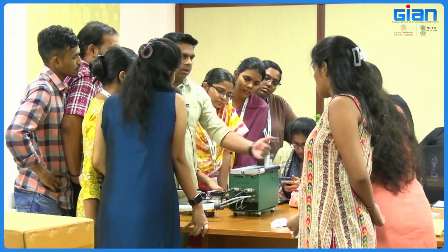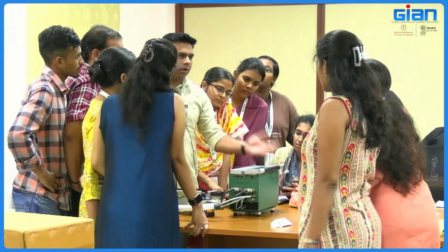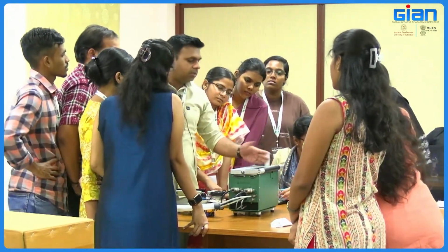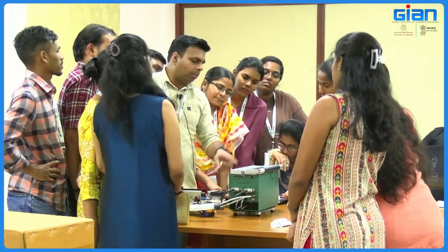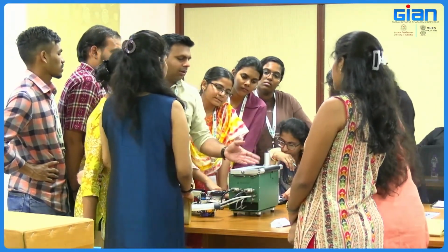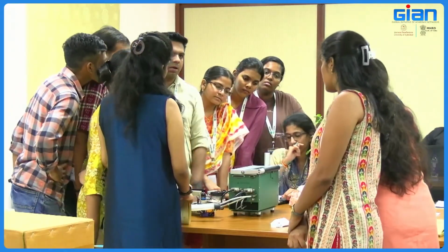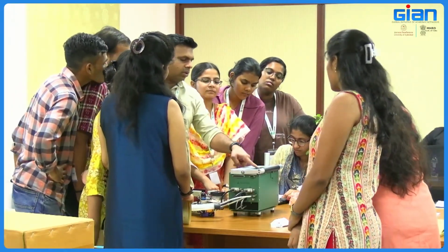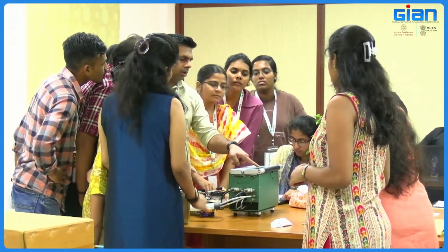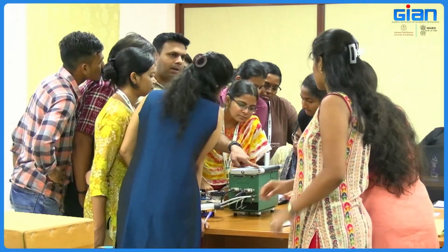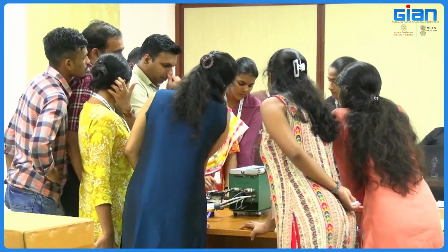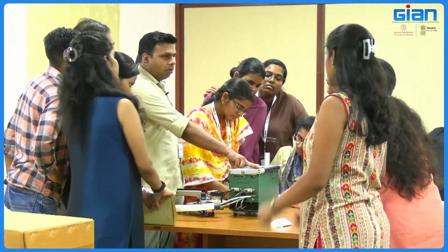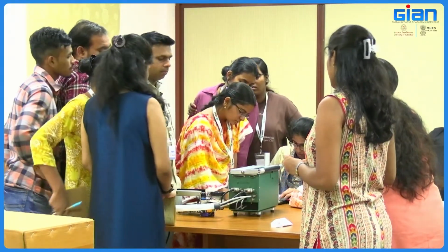Press any key. Everything is mentioned here, no need to go into too much detail, because whatever the readings will need, it will show in here. So you just press any key. It will take some time to zero the IRGA. Okay. So these two readings should be around the same. It may not be 0, but the readings should be the same.